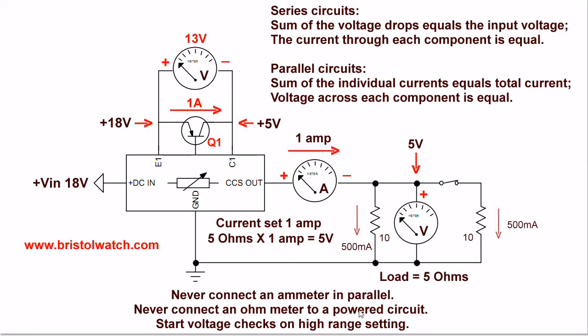Never connect an ohm meter to a powered circuit. If you're going to use it in the ohms range, turn off the power. When you're checking voltage, don't start at the lowest voltage setting. Start at a high voltage range and come down after you've done some checking. I've done troubleshooting for about 50 years. Believe me, you will save a lot of grief. And even after all these years I can occasionally make a mistake. That's just normal, just be aware of it.